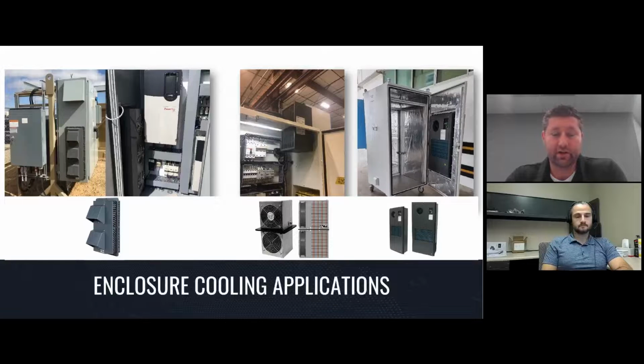The middle photo is our heat pipe cooler. The bottom image shows a cross section of the HPC, with the copper-colored heat pipes visible. These are straight heat pipes using methanol as the working fluid, transferring heat from the hot air inside the cabinet to cooler outdoor air. Heat pipes are an extremely efficient mechanism for transferring heat at a very low delta T, which drives down the cutout footprint needed on the cabinet. This example is mounted on top of an electronics enclosure driving machinery in a machining factory.